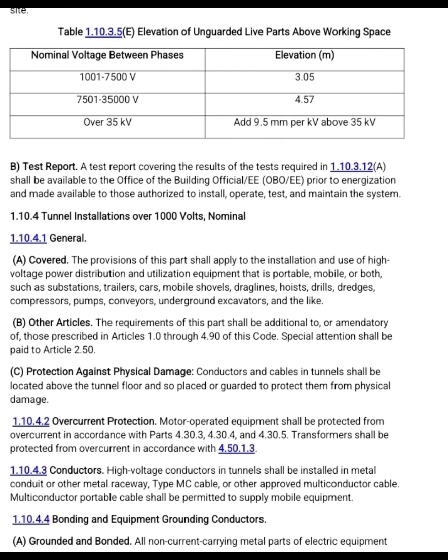Table 1.10.3.5 E. Elevation of unguarded live parts above working space. Nominal voltage between phases 1001 to 7500 volts, elevation 3.05 meters. 7501 to 35,000 volts, elevation 4.57. Over 35 kilovolts, elevation: add 9.5 mm per kilovolt above 35 kilovolts.